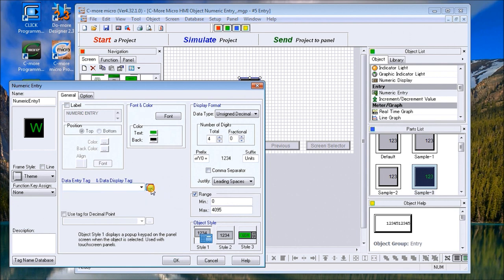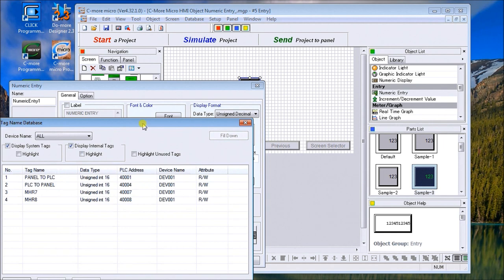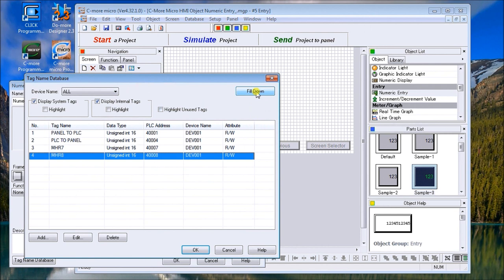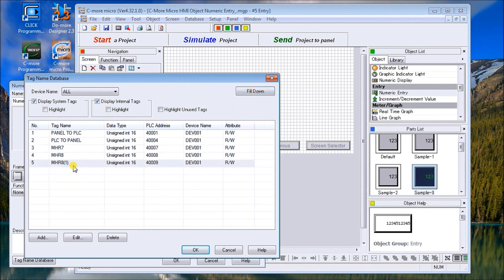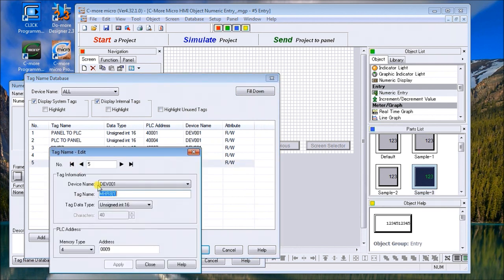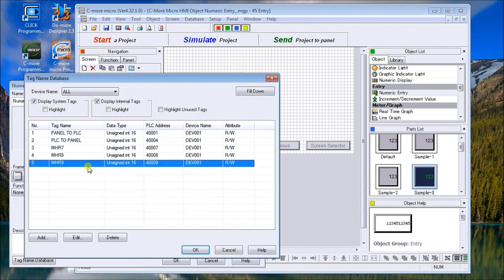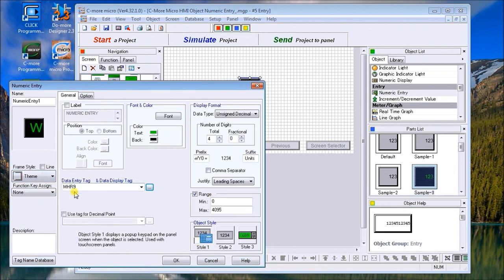Let's call up our tag name database. We'll use the fill down, which will do the next available tag in our series, which will be the PLC address 40009. So we'll fill that down, and that represents the tag name and the MHR9. We'll change that to 9, hit apply. There's your memory type is 4 and the address is 9. We'll close that off. It's an unsigned integer 16 bit, hit OK.